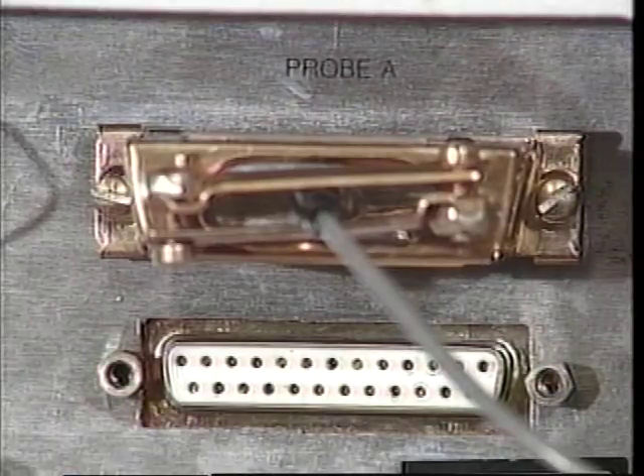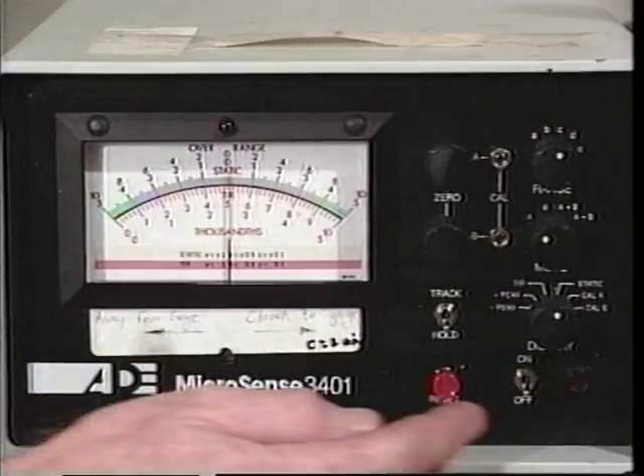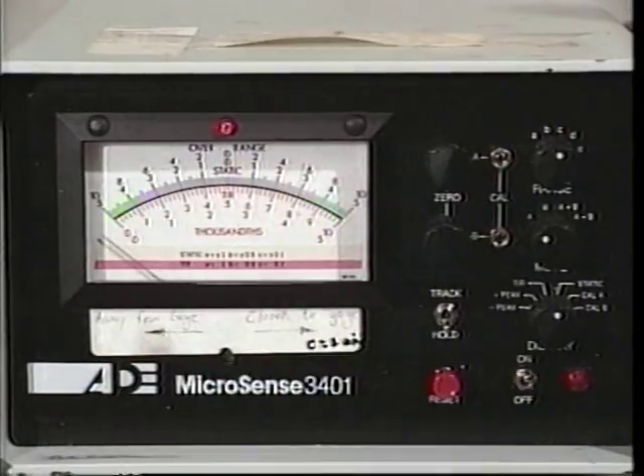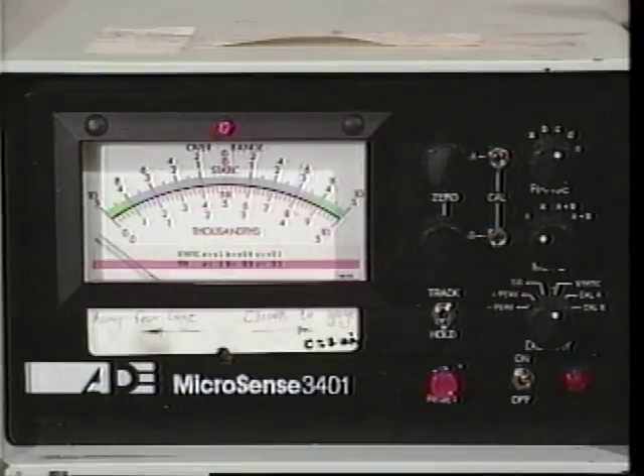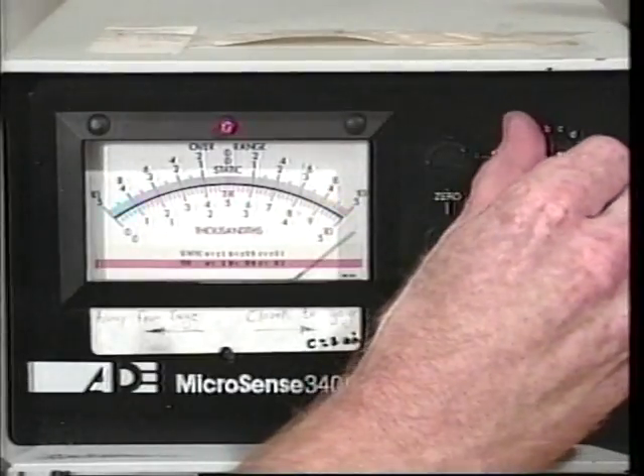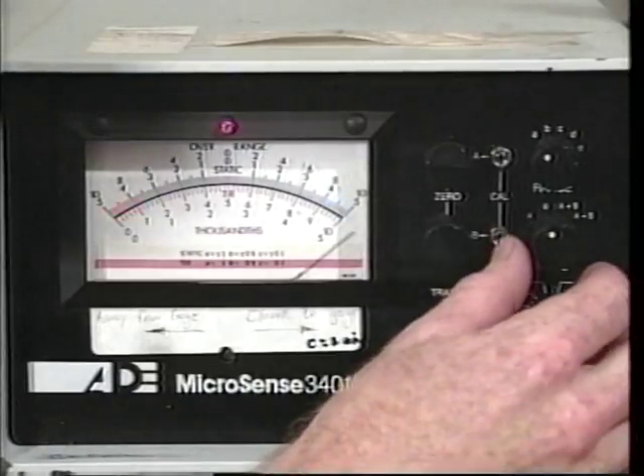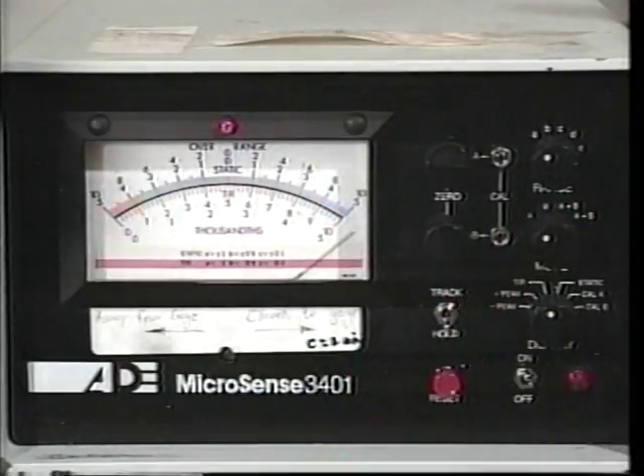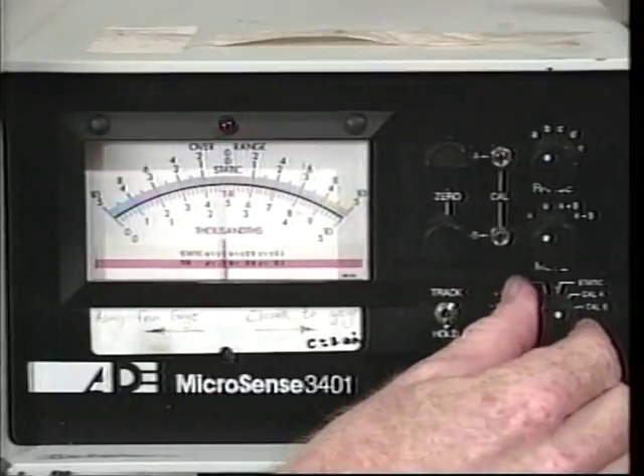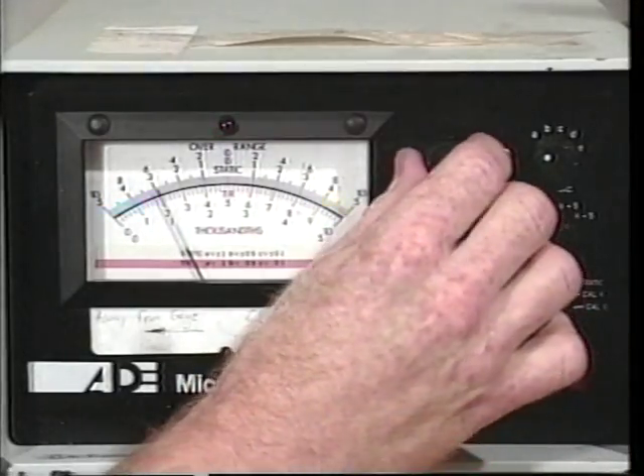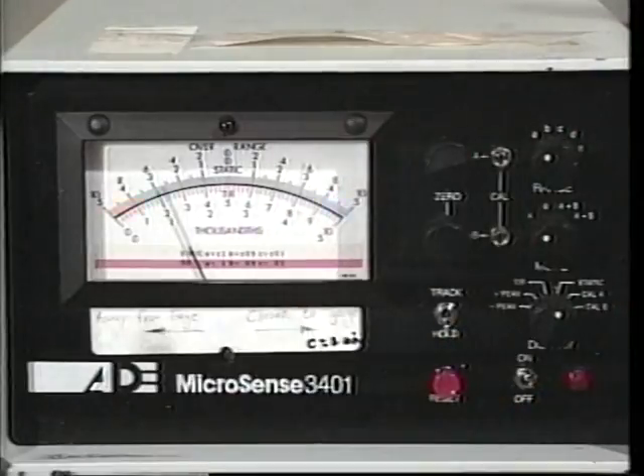To make a displacement measurement with this cap gauge, first ensure that the probe is secured to the appropriate connector on the rear of the console, that is, probe A with connector A. Power up the console and allow time for electronic stabilization. After warm-up, select the channel matching the probe being used. Select range A, the range with the largest measurement spread. Select the mode desired, which in this case will be A. Select the display mode to static. Position the 10-turn electronic fine adjust knob in the middle of its range.